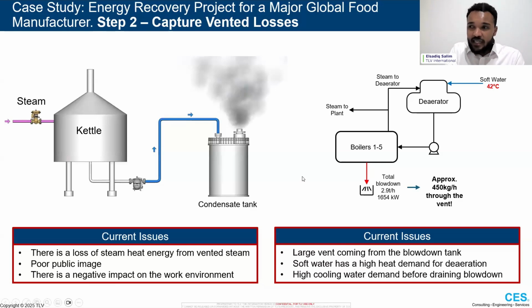So whenever we see vents like this, we need to think about, okay, how can we capture these vented losses best? So we've got two case studies here. The one on the right-hand side is in that food manufacturer, and the one on the left is a general diagram. One is where we've got condensate tanks and steam being vented out of the condensate tanks. Again, very normal. As long as it's not affecting our process, it's no direct issue. However, this is definitely an energy loss, which the site was interested in recovering.